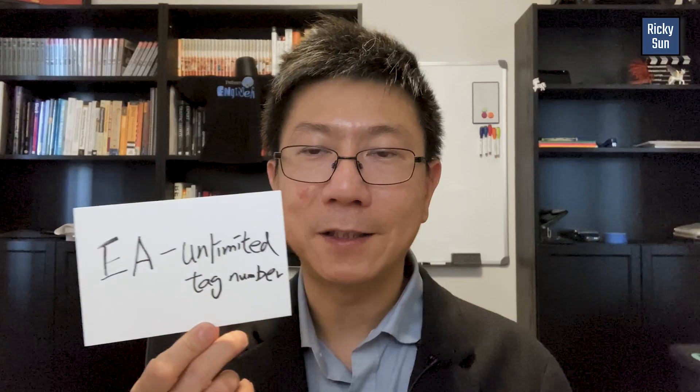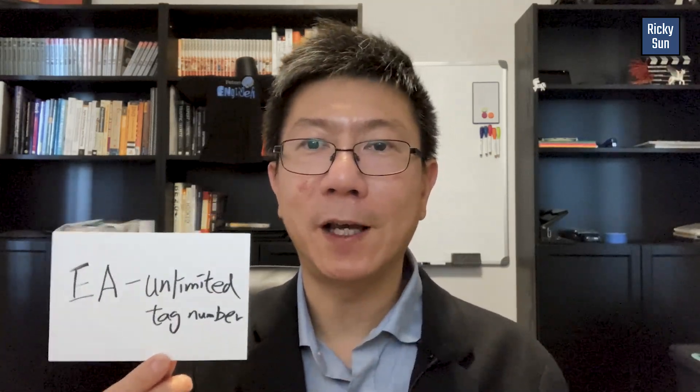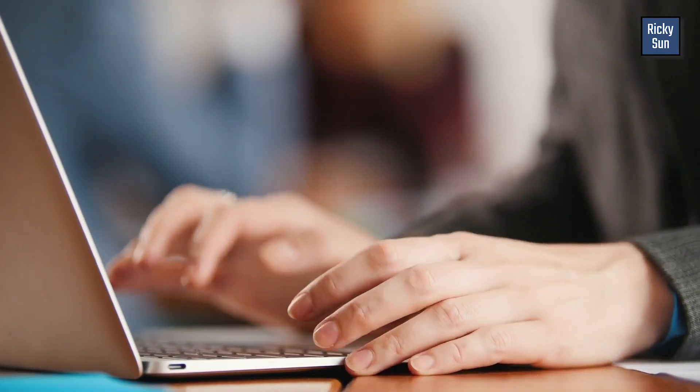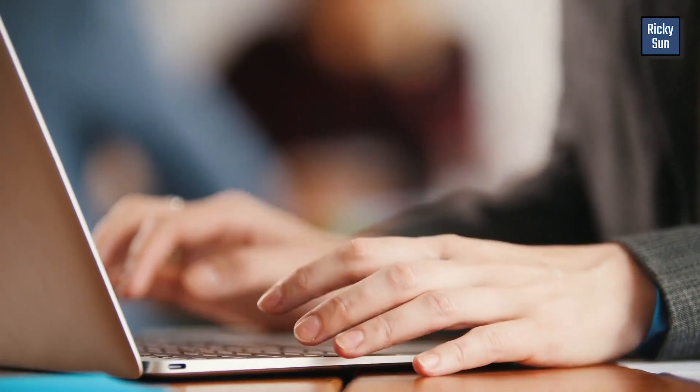It might not be a problem for EA customers. When I was working with OSIsoft, EA customers can create an unlimited number of tags, so you don't have this problem — but you still have created a lot of tags that are not updating. You should turn them to scan off so they're not impacting your PI server, and make some indication that this tag is never going to update. Instead of just leaving the tag looking normal when it might or might not be updating, as a PI administrator we should put some indication there saying this tag got decommissioned and is no longer updating.